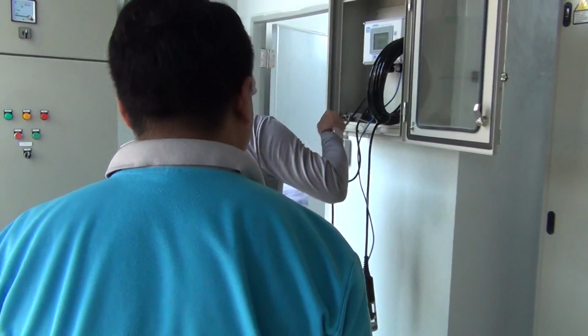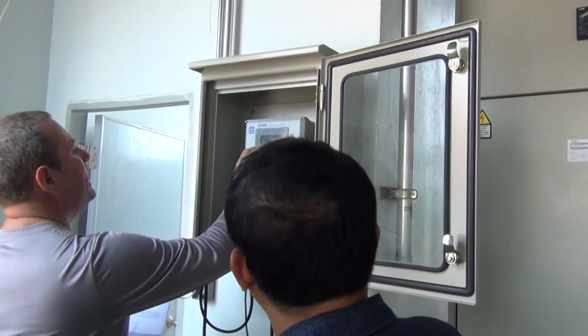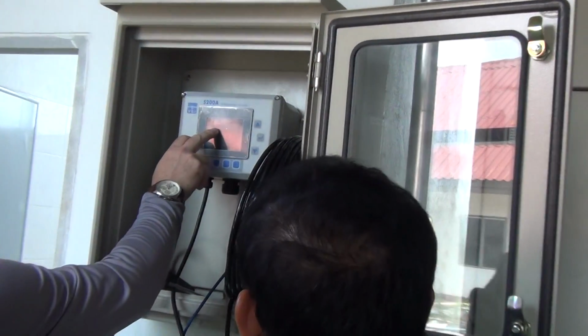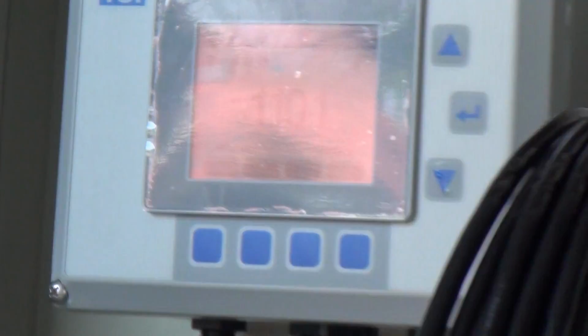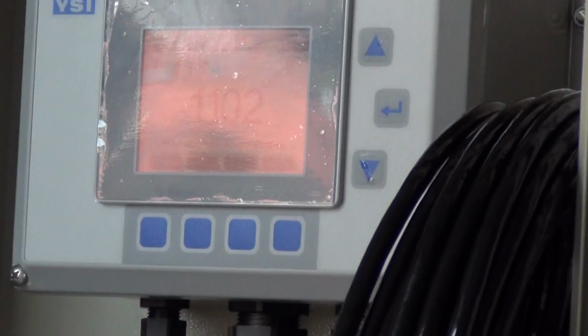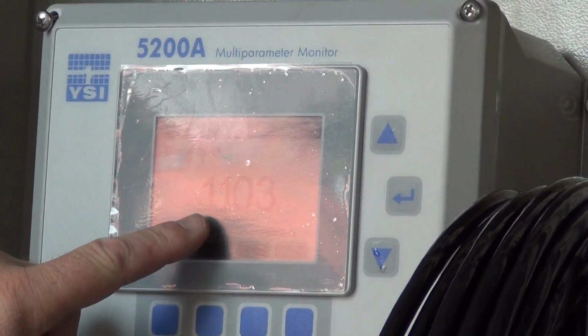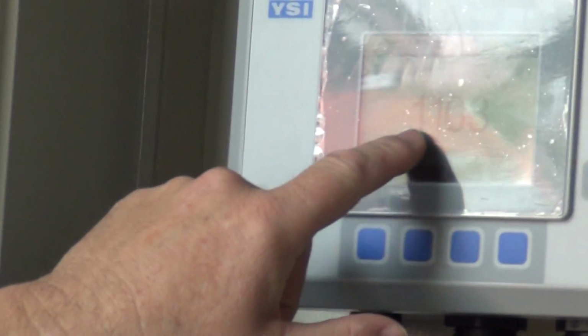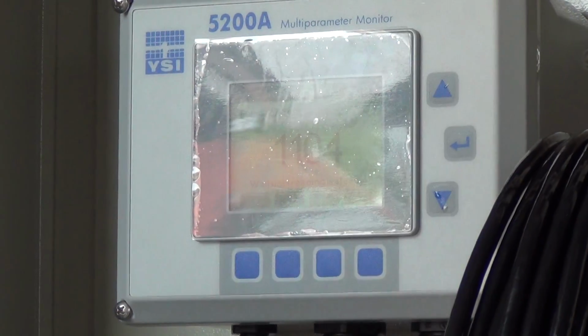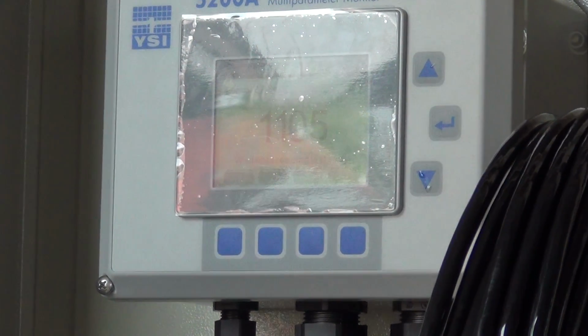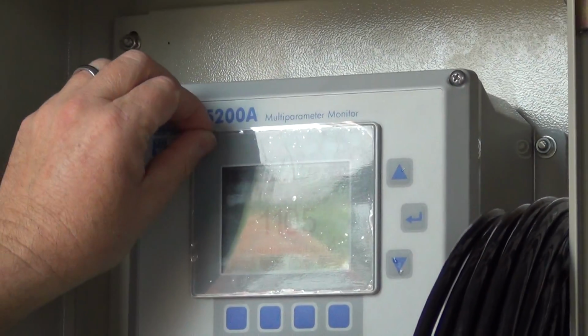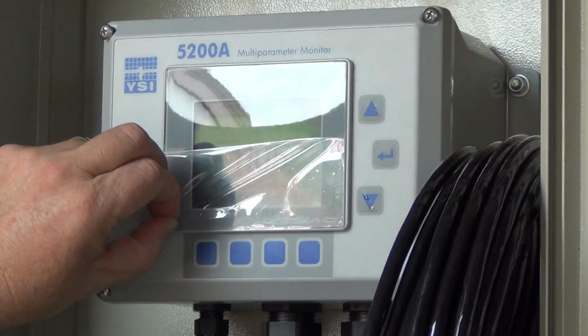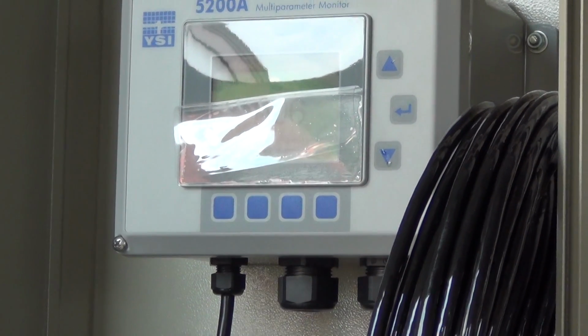Let me see what our temperature is. Temperature is indicated at 27.2. So it's 2.2 degrees above the standard, because the standard is set for 25 C, right? So at 27.2, we're slowly climbing. We were at 1100, we're now at 1104. We have to wait for this to stabilize. What's interesting is the temperature is also climbing, which is why the reading is climbing.